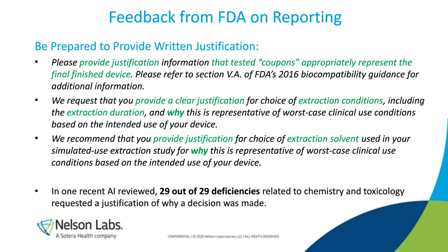They said, we recommend that you provide justification for choice of extraction solvent in this simulated use extraction study and why it's representative. So again, it's not just picking one off of an official list. We have to understand and explain the why part.